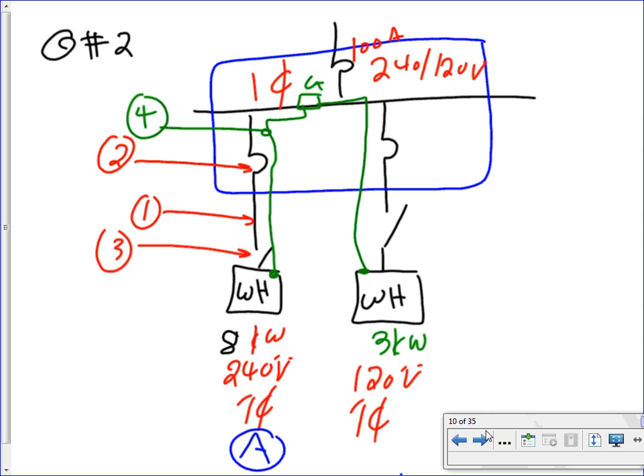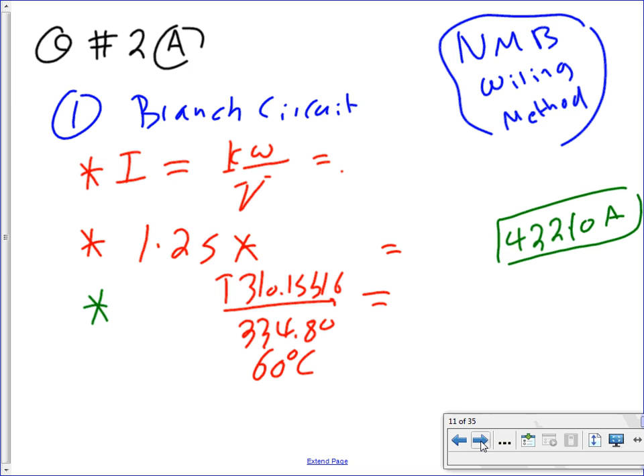Okay. Shall we move? Yes. Okay. Here's the first thing we need to do. I want to quickly remind you, my friends, that we are still using an NMB wiring method, so we're still limited to the 60-degree column. Next project, guys, you're going to use an MC cable, so you're going to start using 75 or 60, depending upon the size of the conductor.